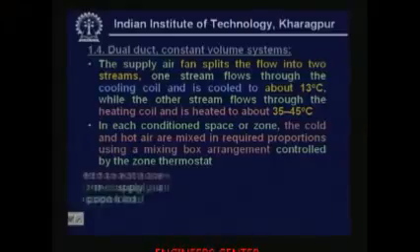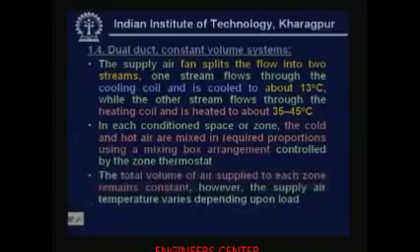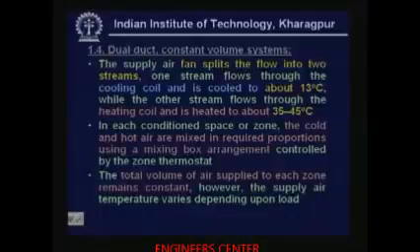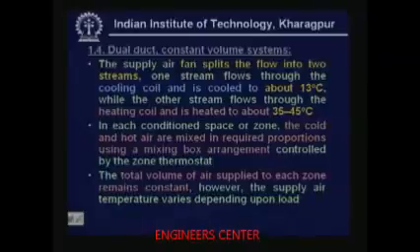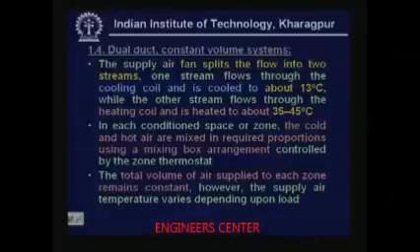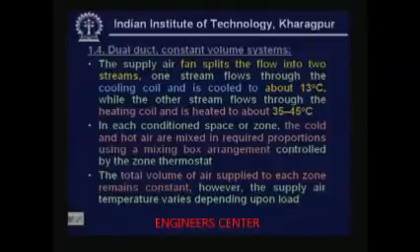This is a zone thermostat. The total volume of air supplied to each zone remains constant. However, the supply air temperature varies depending upon the load. So remember that this is a constant volume system — we are keeping the total volumetric flow rate constant, but varying the supply air temperature.